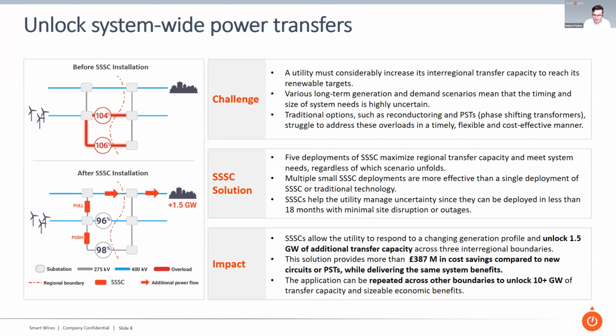What I have on screen here is one of the applications Marie was talking about at the start. She was talking about resolving thermal overload specifically on transmission grids. On the left-hand side is shown a simplified diagram of where you end up reaching the thermal limit of a line under certain contingencies. In this case, it's 2 parallel circuits. This specific case study was when a utility wanted to increase their renewable connections in one location in the country, and they had drawn a number of boundaries across the country and wanted to increase the transmission capacity across those boundaries. The issue is that there was uncertainty in the timing of the connection of generation and demand, and the traditional solutions, reconductorings, PSTs, operating of transformers, things like that, didn't provide the same level of flexibility that you could achieve using the SSSCs.